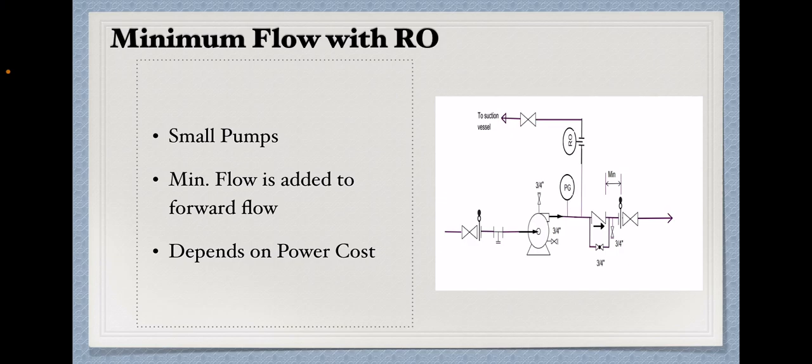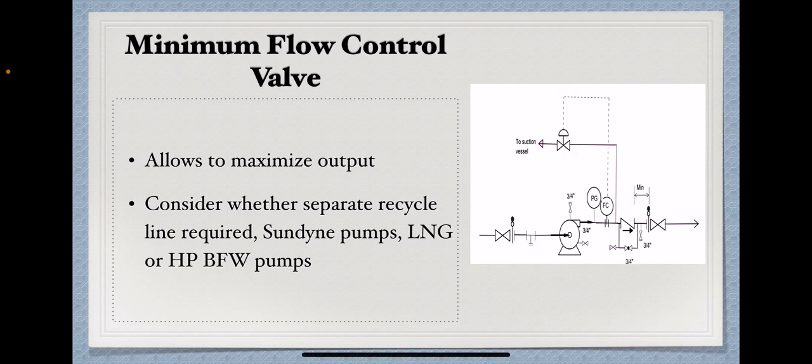Now, the option two is the minimum recirculation line with the control valve on it. Here we can see that the minimum recirculation line takeoff is at the upstream of the check valve and there is a flow meter upstream of this recycle line...